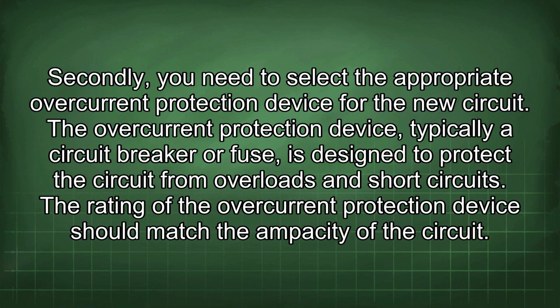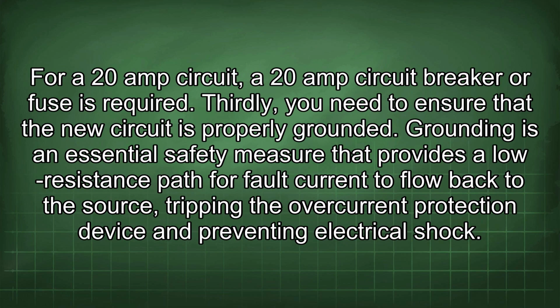Secondly, you need to select the appropriate overcurrent protection device for the new circuit. The overcurrent protection device, typically a circuit breaker or fuse, is designed to protect the circuit from overloads and short circuits. The rating of the overcurrent protection device should match the ampacity of the circuit. For a 20 amp circuit, a 20 amp circuit breaker or fuse is required.